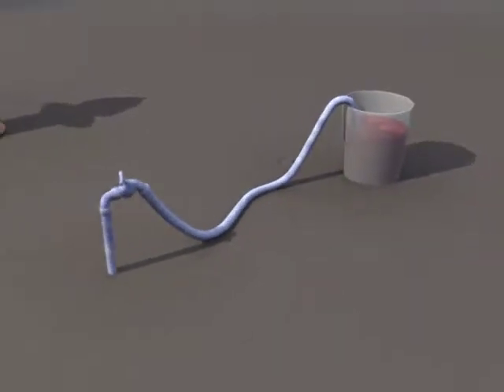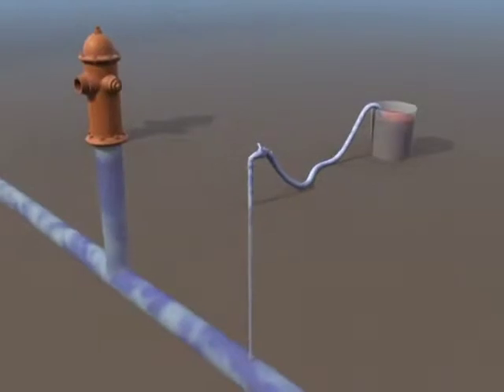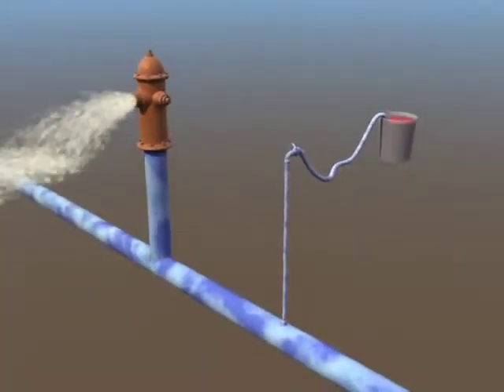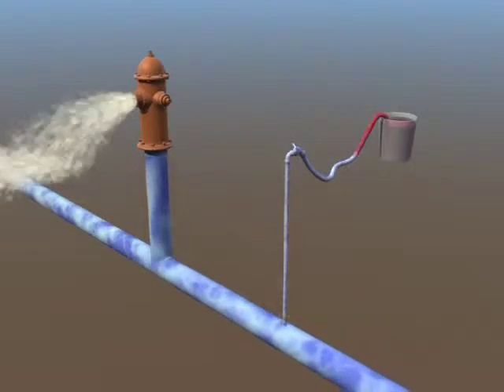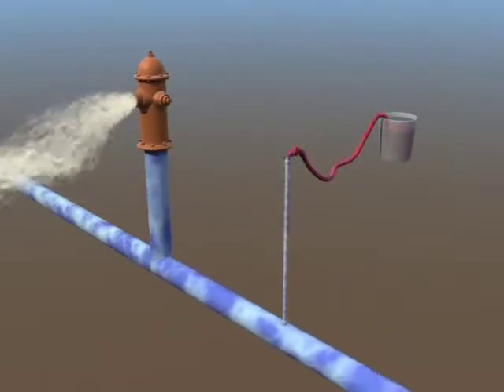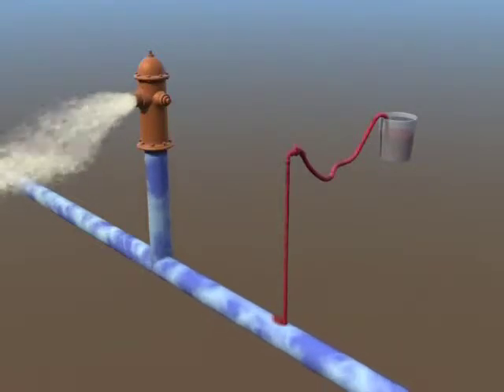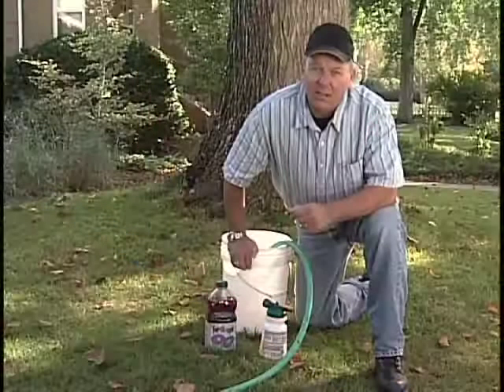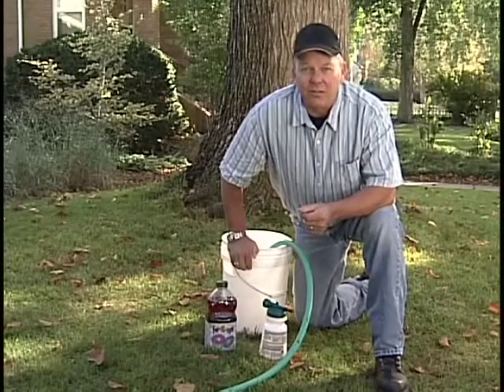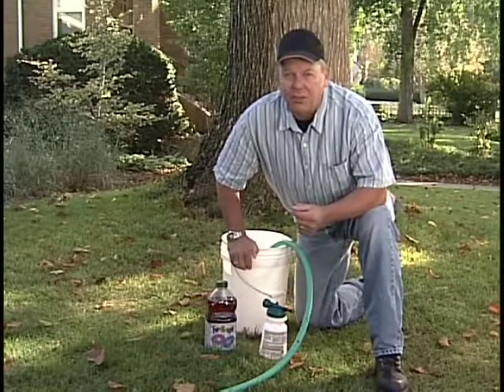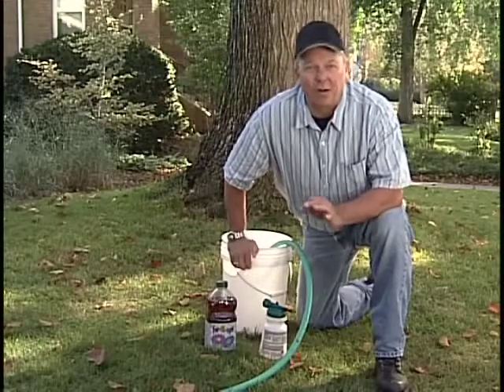After a few seconds, the fire department begins to fight the fire and pulls a tremendous amount of water out of the water system. This might create a backflow in the system, and let's use our animation to show how this might all work. Potentially, the water in this hose can start to be sucked backwards. This could easily pull the contents of this bucket into the water system. The backflow created by the open fire hydrant pulls the water backwards, sucking the fertilizer back into the hose and eventually into the water distribution system. So, the backflow created in the water system by the firefighting and the cross-connection between the hose and the bucket contaminates the water system.